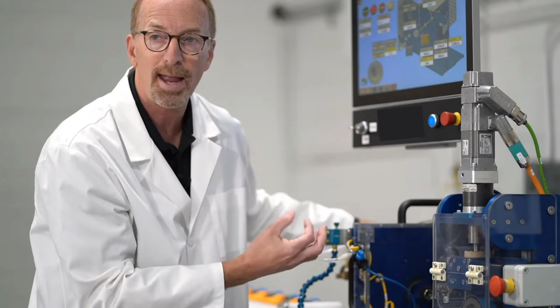Other things for cleaning, just like in the tanks, we want to be able to clean this area out and make it very visible so you can see the blade, and see if particulate's building up on the blade. People hate the word particulate, but particulate is a bad thing for medical tubing, whether it's a hair, a piece of dust, or a piece of flash. There are three different types of particulate.